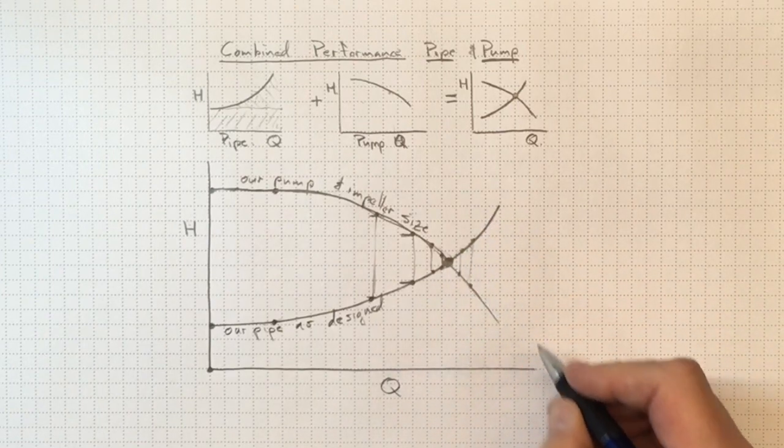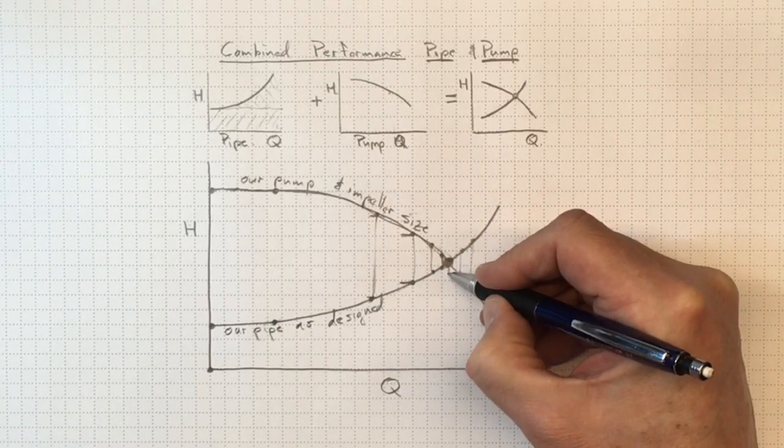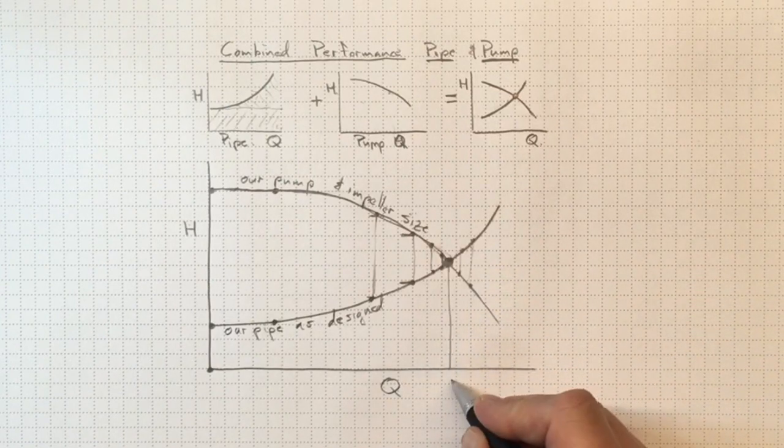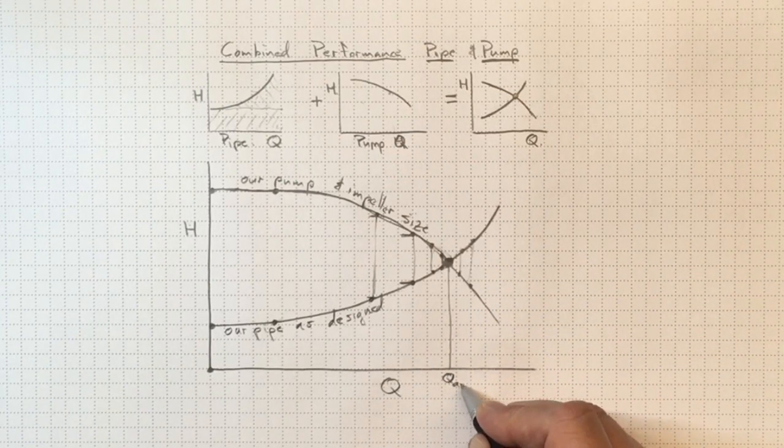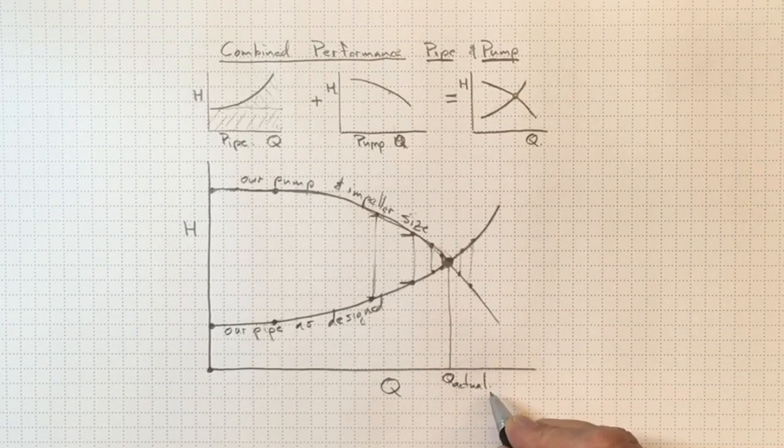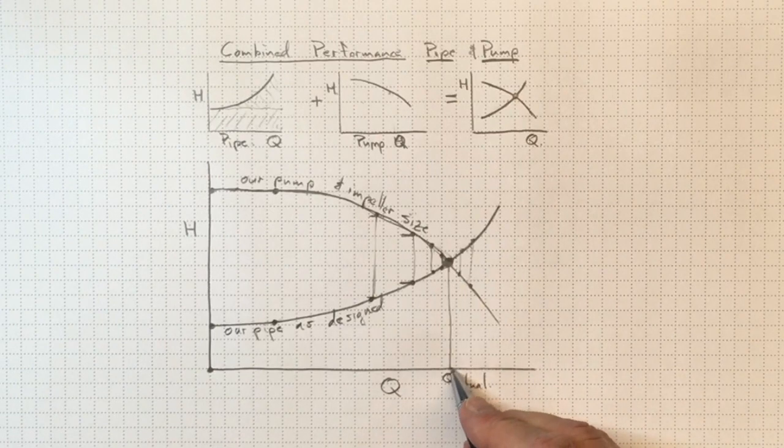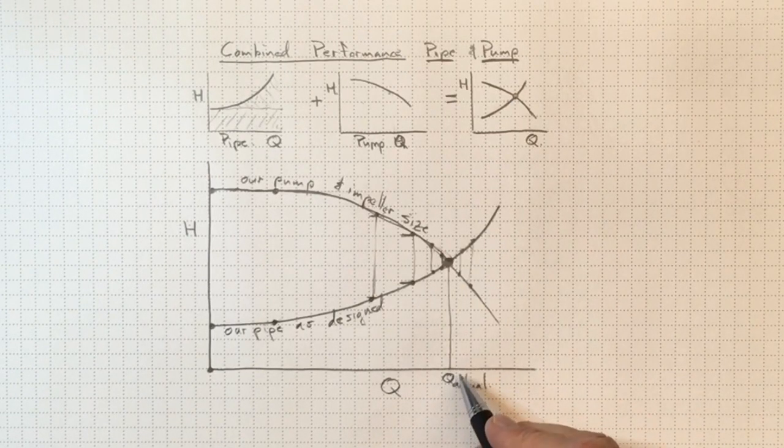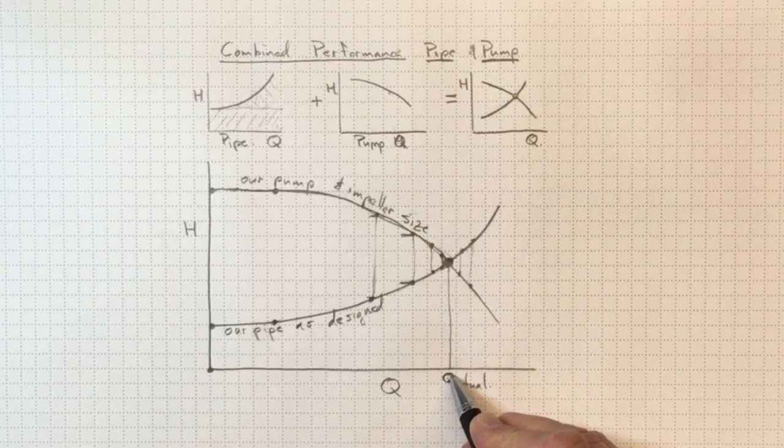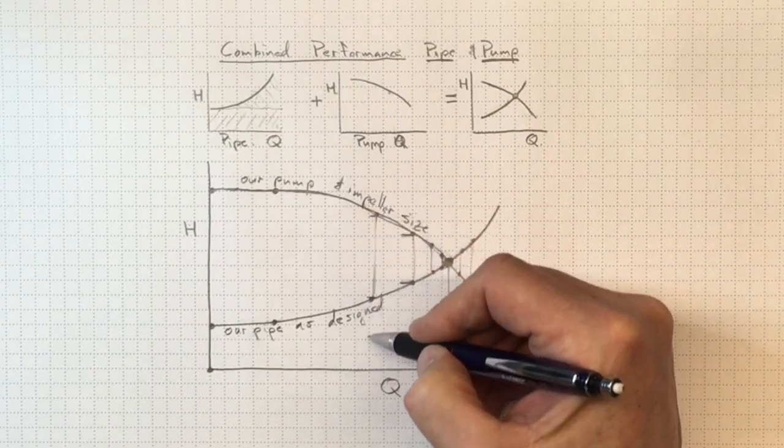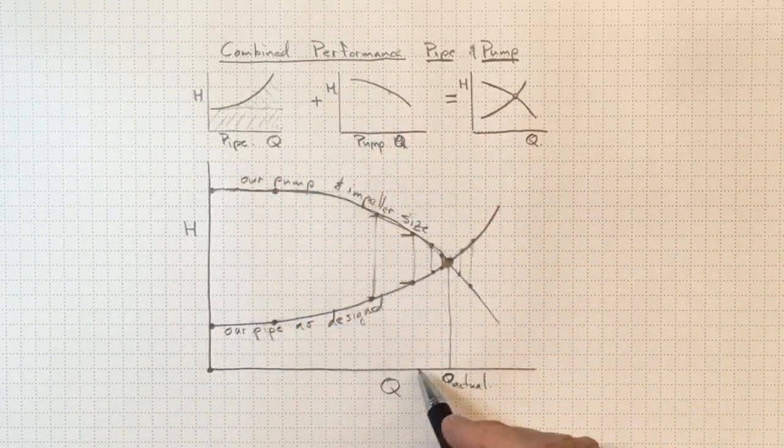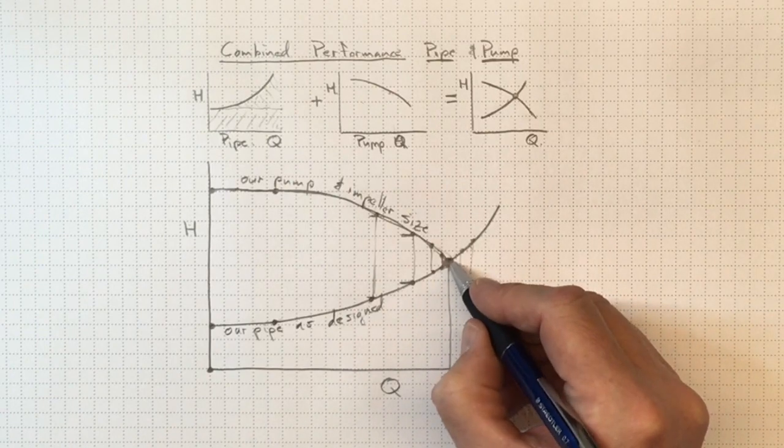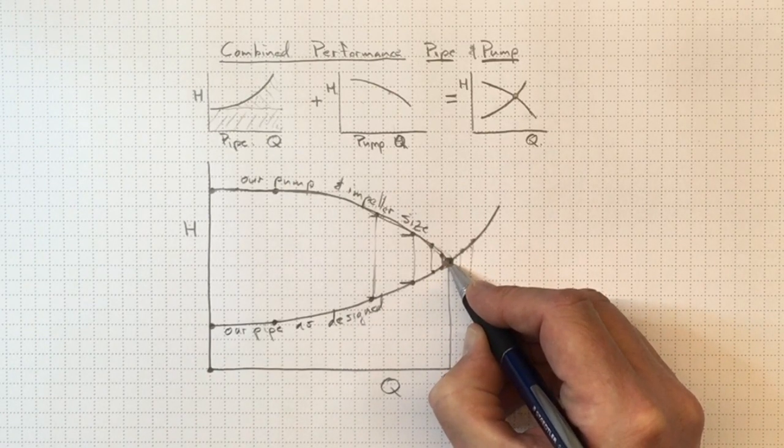And once we know what that operating point is, we can figure out what our actual flow is going to be that goes through the piping system. It may not be what we designed for, it may be something rather different than that. We might have designed for over here, but because we picked a pump that was somewhat oversized, if we just switch things on, we wind up operating out here.